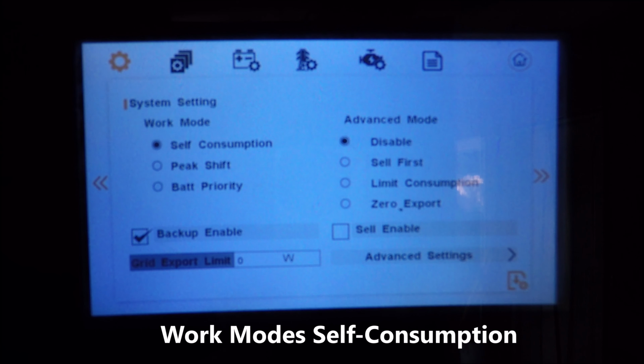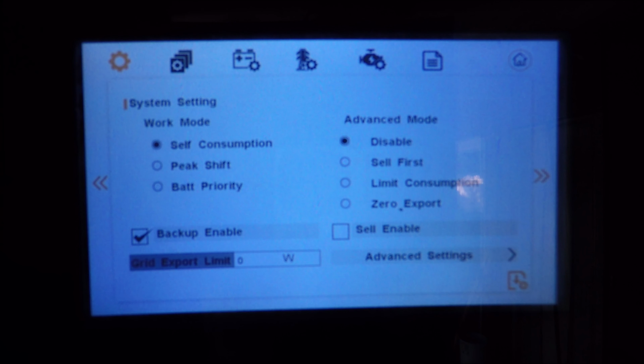Self-consumption sets the inverter to be your own power grid. It manages the PV arrays, the batteries, the grid, and the generator input to provide power. Self-consumption will prioritize loads and, when configured correctly, can also grid feed and grid sell. My setup, I do grid tied. Grid tied means I do pull in power from the grid and I use that with the inverter to mitigate the demand from my loads. However, I do not grid feed, which is I keep the inverter configured to ensure that it does not feed back electricity to the grid.